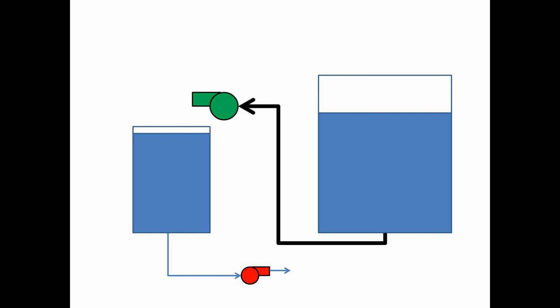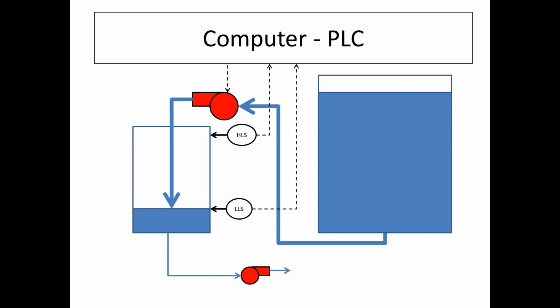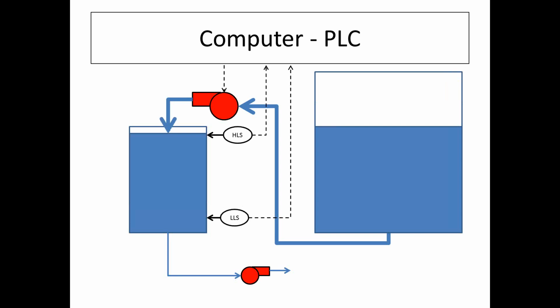So even though it's not complicated, the operator needs to devote a lot of their time and resources to just monitoring that process. On the other hand, if you add a little bit of instrumentation and a little bit of programming to this, it simplifies the process entirely. When the level gets down to that low level switch at the bottom of the tank, that low level switch sends a signal to the PLC computer, which turns the large transfer pump on. And then that goes ahead and starts filling up the day tank.